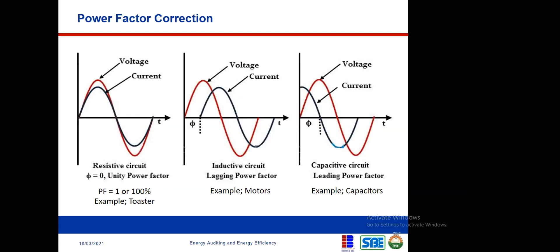So now we'll have to look at kVA. That is, how do you correct that waste? The kVAR in your system. In trying to correct that, remember I talked about capacitors. If you have a power factor that is less than 100, you need capacitive load to drag it up. So how do you determine the size of the capacitor that you need?